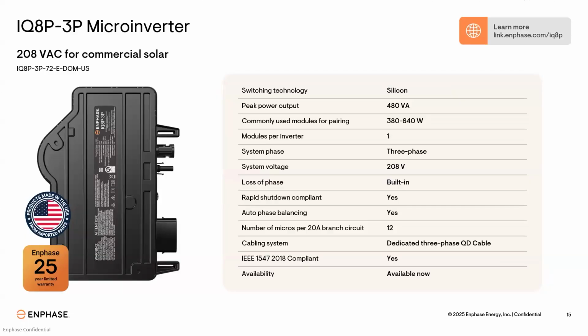This IQ8P 3P, this is a 208 volt microinverter. This is available today. You can walk in anywhere and pick this up. Few differences, obviously, from the 480 volt one. This is a 208 volt microinverter. The peak power output is 480 volt amps and is typically paired with 380 to 640 watt modules.